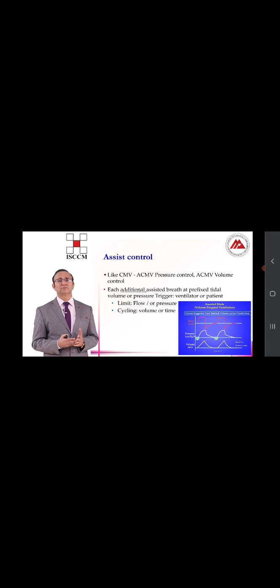None of the ventilators has a separate knob for control or assist control. There is a single knob. If the patient is paralyzed or is apneic, then it becomes a pure control, and he will only get the breath and the tidal volume or the pressure which you have set on the ventilator. But if the patient is not paralyzed, it becomes assist control. So that means the patient can trigger and get the mechanical breath from the ventilator.